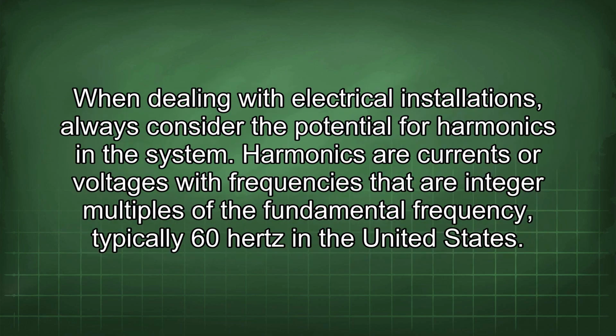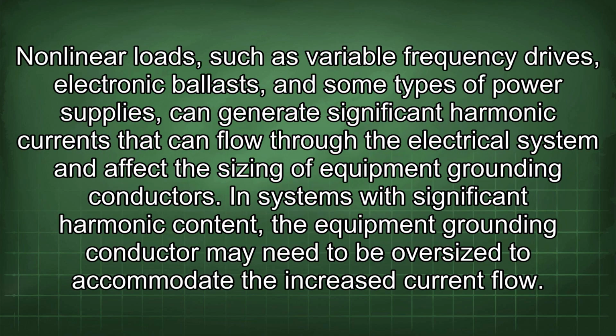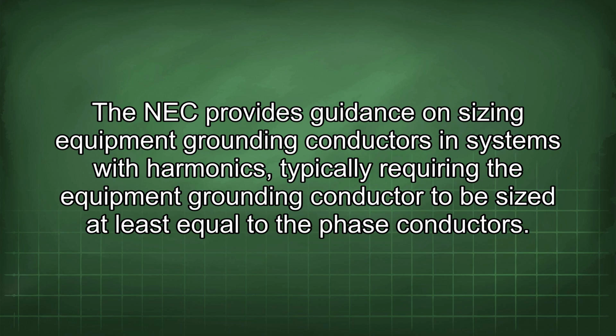When dealing with electrical installations, always consider the potential for harmonics in the system. Harmonics are currents or voltages with frequencies that are integer multiples of the fundamental frequency, typically 60 Hz in the United States. Nonlinear loads such as variable frequency drives, electronic ballasts, and some types of power supplies can generate significant harmonic currents that can flow through the electrical system and affect the sizing of equipment grounding conductors. In systems with significant harmonic content, the equipment grounding conductor may need to be oversized to accommodate the increased current flow. The NEC provides guidance on sizing equipment grounding conductors in systems with harmonics, typically requiring the equipment grounding conductor to be sized at least equal to the phase conductors.